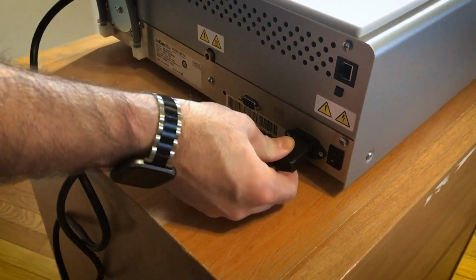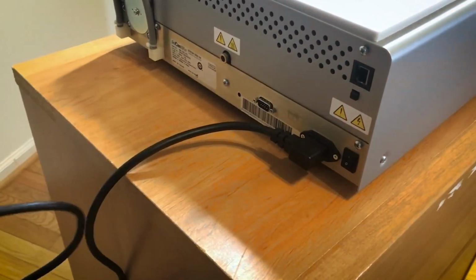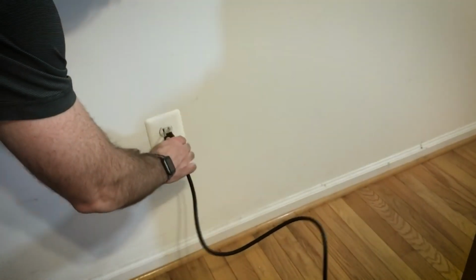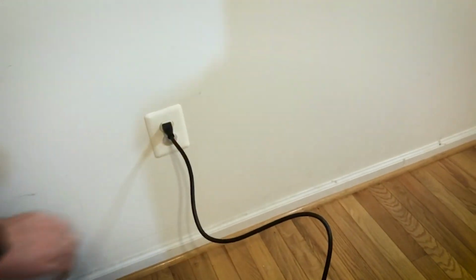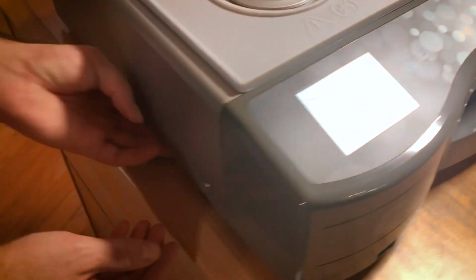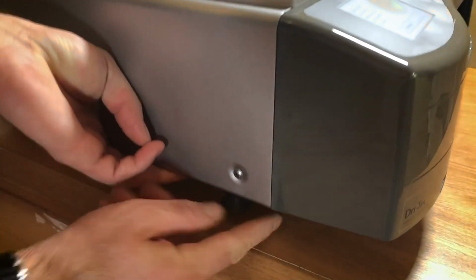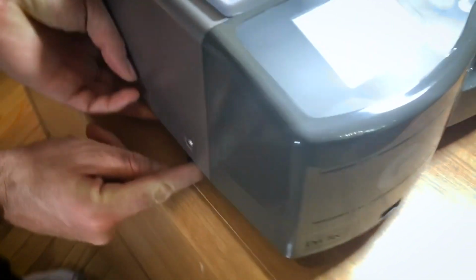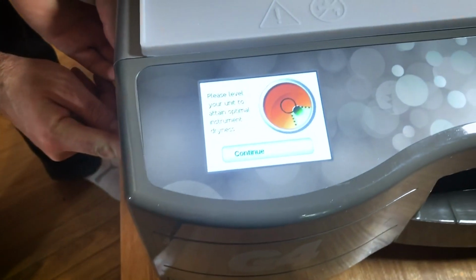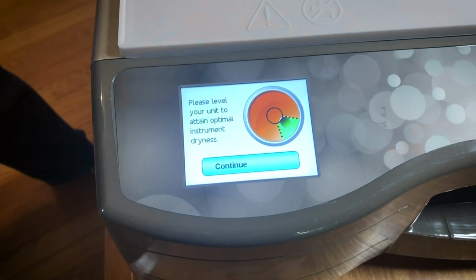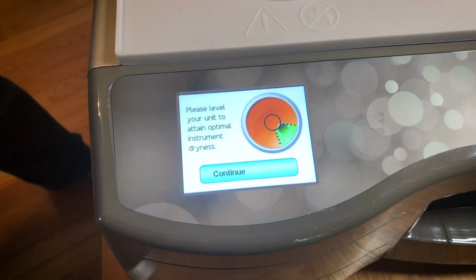And of course, since it is an autoclave, the first thing we're going to need to do is obtain a power source and plug it in. Next, we need to find as level of an area as we can. It doesn't have to be perfect because the autoclave does have some adjustable legs that allow us to level it out. And the icon on the machine will actually tell us when it is not level and when it is level. So once we get that adjusted and in place, we can move on to connecting the waste bottle.